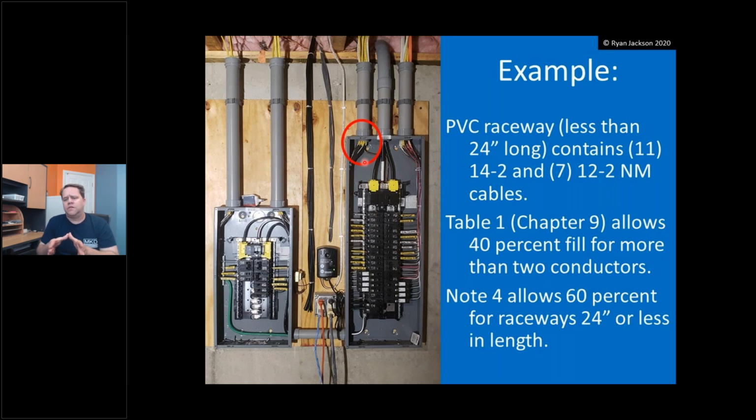The guy who did this is a guy named Phil Mazzara. It's a great installation, by the way, and he posted this on Facebook, and I immediately said, this is a violation. And he insisted that it wasn't, and I said, oh yeah, well, I'm going to do the calculations, and I'm going to show you why this doesn't comply. And we're going to find out who was right and who was wrong. But he said, listen, this is exactly 18 inches, and we can see that it's less than 24 inches long.